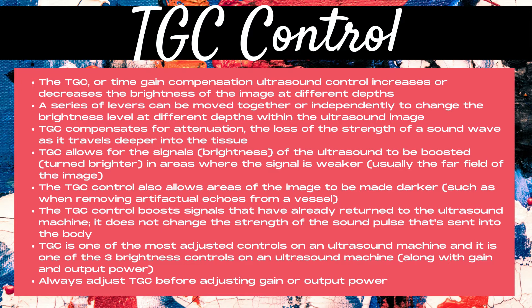The TGC control compensates for the ultrasound concept of attenuation — the loss of the strength of a sound wave as it travels deeper into the tissue or through a dense structure on an ultrasound.